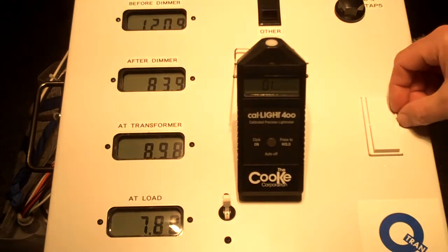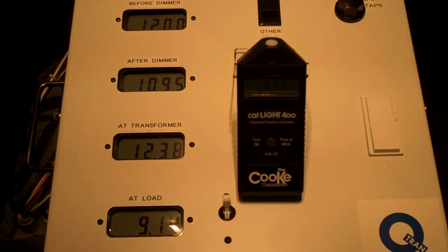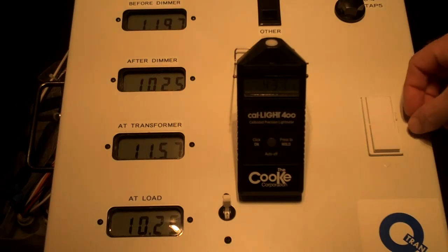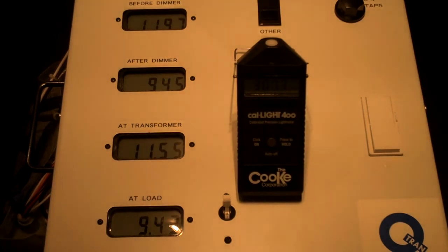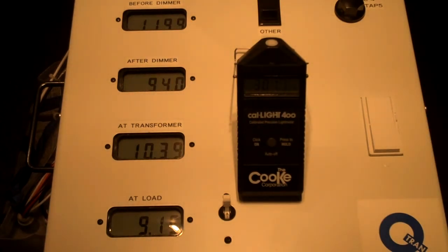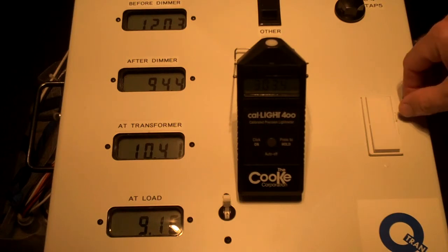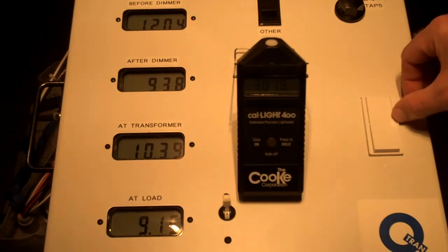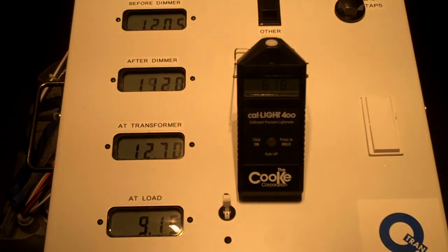Dimming just 10%, which is about right there, doubles your lamp life. So you can take a 5,000 hour lamp, make it a 10,000 hour lamp. Dimming 20% quadruples your lamp life. So you take that 5,000 hour lamp, it's now a 20,000 hour lamp, thus reducing energy as well as reducing your maintenance costs. Periodically, if the lamps begin to darken, per the cut sheets from the manufacturers, you merely bring it up to full voltage for 15 minutes. The lamps will self-correct and clean themselves.